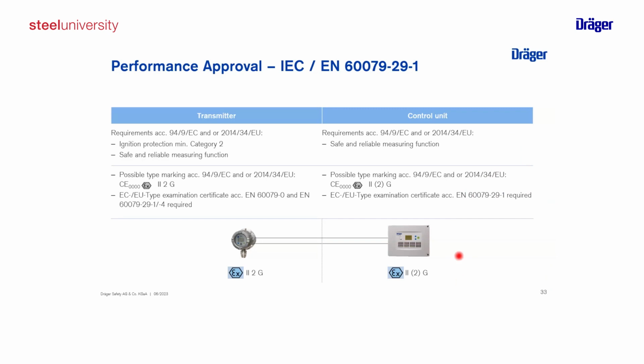You find this by the marking on the device or in your examination certificate, where it is stated that the detector, for example, can be used in zone 1 for gas atmosphere. If you use the sensors for primary explosion protection, so that you measure gas concentration and you have a control system which activates, for example, the switching of a ventilation or an emergency shutdown, then the control system also has a big impact on your complete system here.